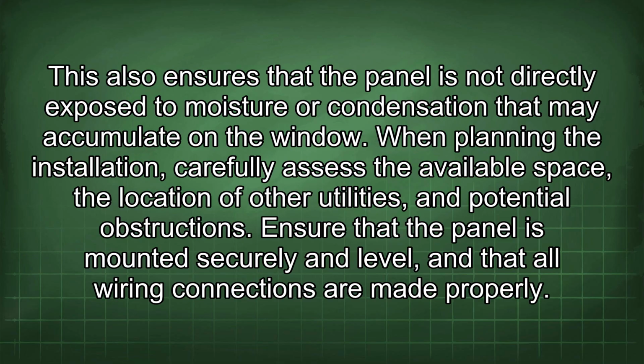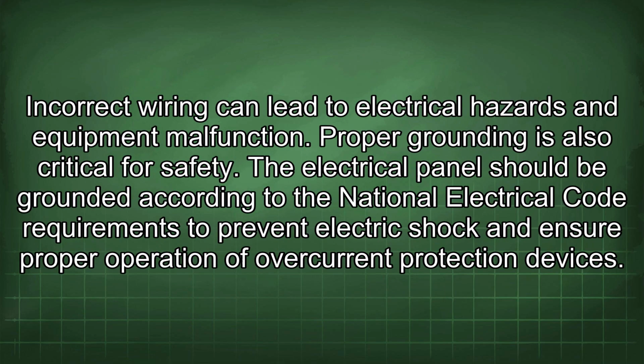When planning the installation, carefully assess the available space, the location of other utilities, and potential obstructions. Ensure that the panel is mounted securely and level, and that all wiring connections are made properly. Incorrect wiring can lead to electrical hazards and equipment malfunction. Proper grounding is also critical for safety. The electrical panel should be grounded according to the National Electrical Code requirements to prevent electric shock and ensure proper operation of overcurrent protection devices.